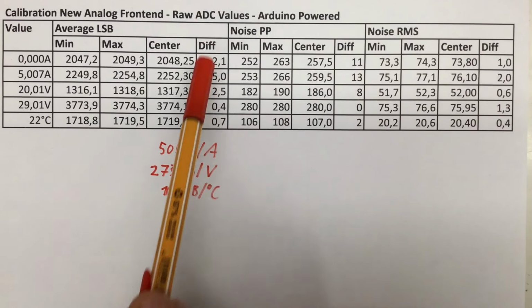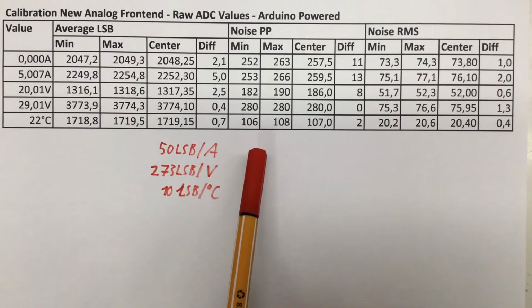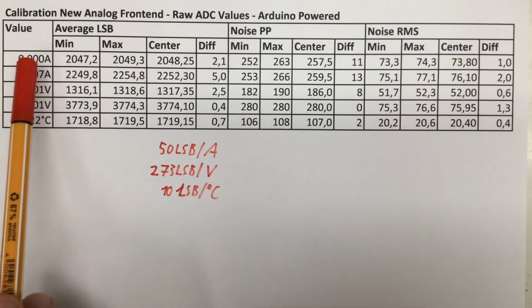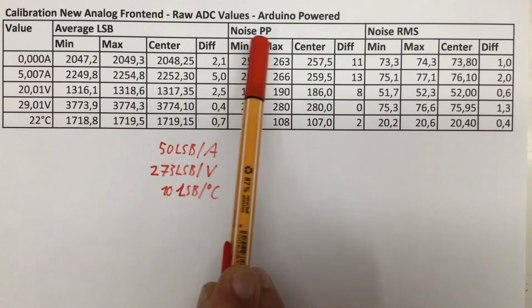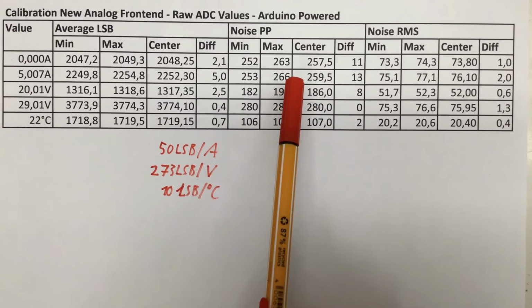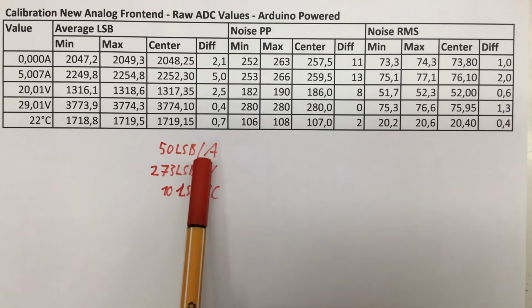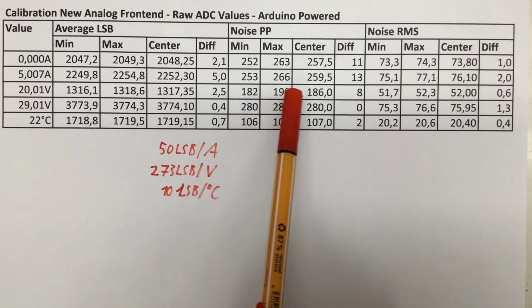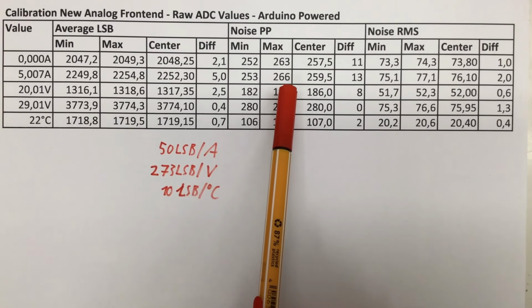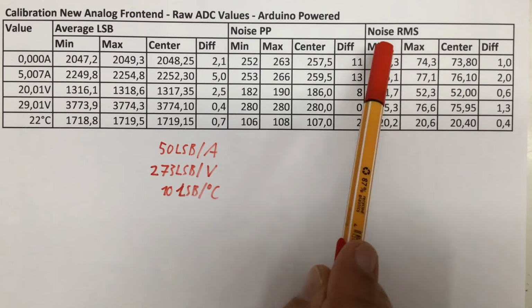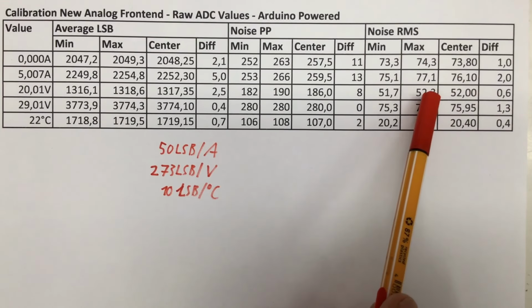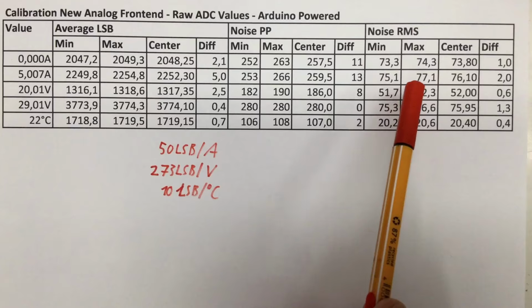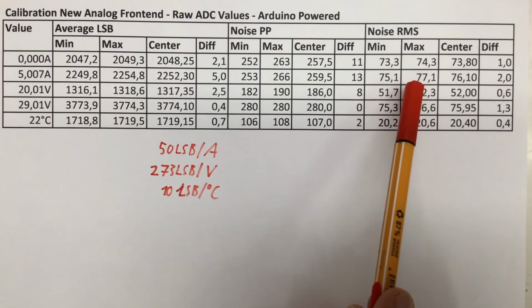If we look at the noise values, that's a whole other story. So here for the current measurements, we have a noise peak to peak of about 250. That's about 5% of the dynamic range of our ADC, or with 50 LSBs per amp, that's about a noise of 5 amps in our measurements. The RMS noise is a bit lower, of course, but it's still in amps about 1.5 amp.